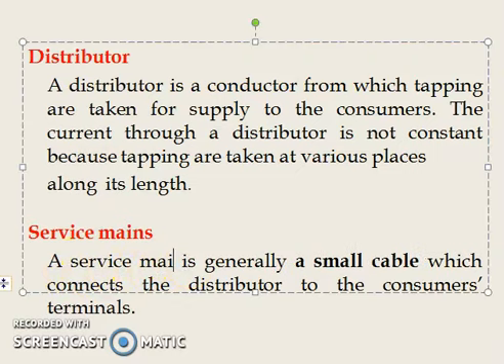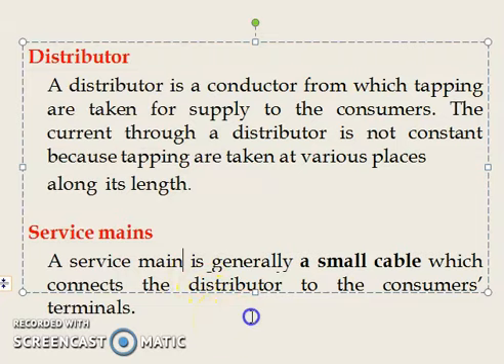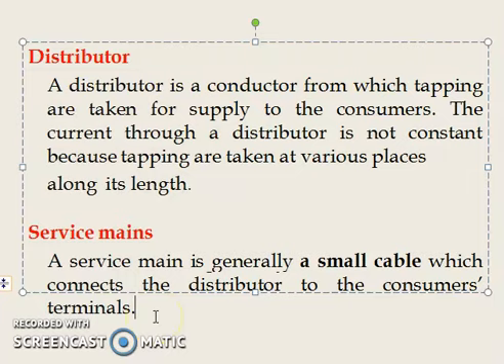Service mains is generally a small cable which connects the distributor to the consumer's terminals. To summarize: a feeder is a conductor with no tappings, and its design consideration is current carrying capacity. A distributor is a conductor where tappings are taken and voltage must be maintained constant. Service mains connects the distributor to the consumer's terminals.